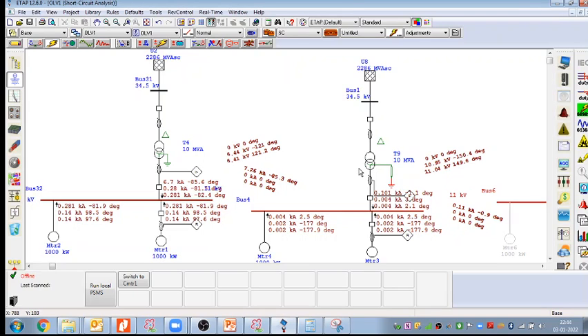Due to the different materials that we use in the transformer and in the motor, the transformer is considered differently. In the transformer we use CRGO type material for the core. When it comes to the motor and generator, it's not the same. So that is the reason. If you want to limit, you can limit. There is no problem, this is your choice. But that is the reason we are not putting it, because we want to have sufficient fault current, so that we can sense the actual fault current. And CRGO is not the same as the motor. That is why.